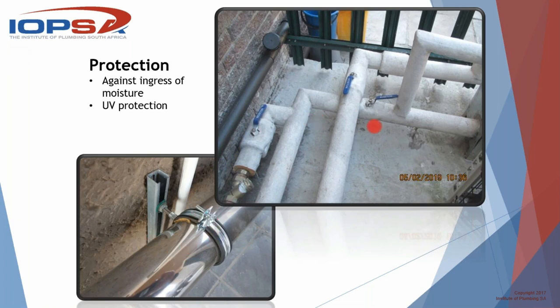Now, here are two examples of very, very expensive and very high-end protection. Yes, these are both commercial installations. So nobody's expecting you to do this for Mrs. Jones in her domestic situation, but I'm just showing you that this is the sort of thing, it is an absolutely necessary thing to do. This is a stainless steel sleeve that goes over rock wool, and this is also a rock wool / glass wool / expanded foam product underneath here, I'm not quite sure what it is, to be honest with you, but it's encased entirely in a fiberglass shell. So they've come afterwards and fiberglassed all over this thing, and that's brilliant, and nothing's ever going to get in there. Yes, if that thing starts leaking, you're going to have to break it open. How do you get to it?